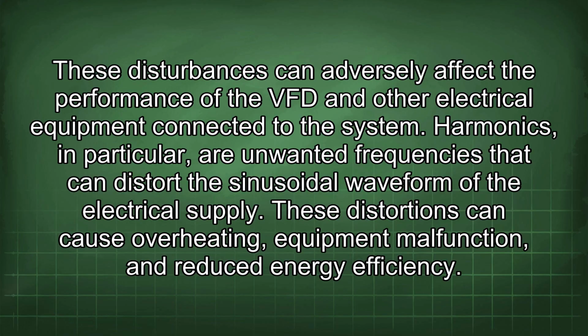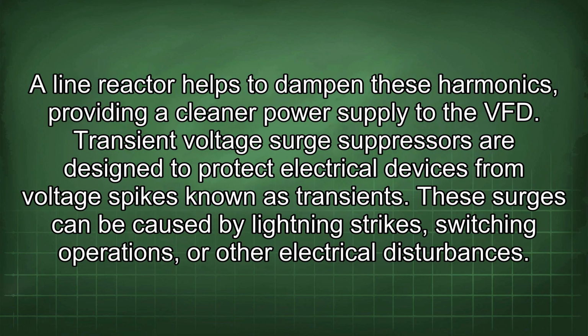Harmonics, in particular, are unwanted frequencies that can distort the sinusoidal waveform of the electrical supply. These distortions can cause overheating, equipment malfunction, and reduced energy efficiency. A line reactor helps to dampen these harmonics, providing a cleaner power supply to the VFD.